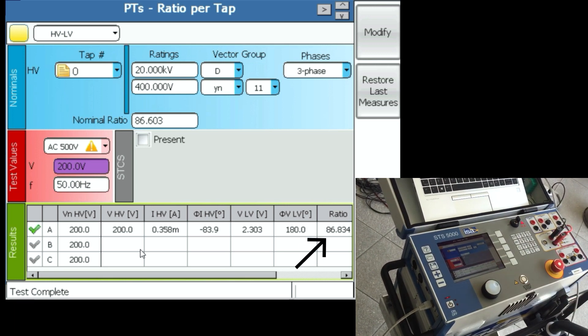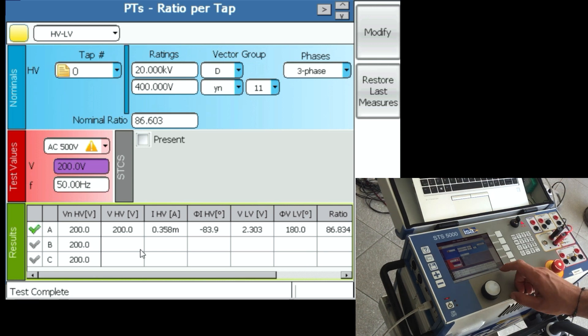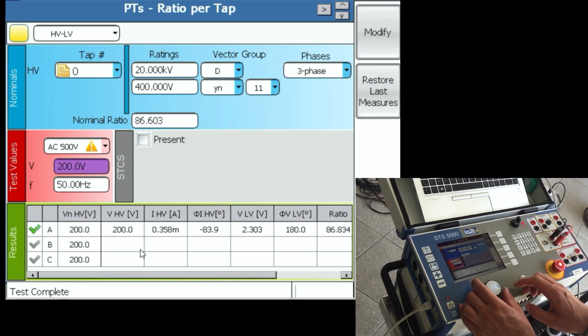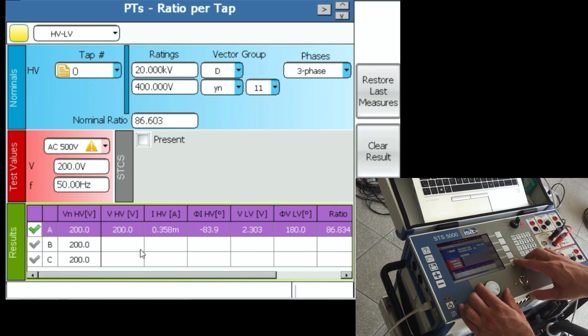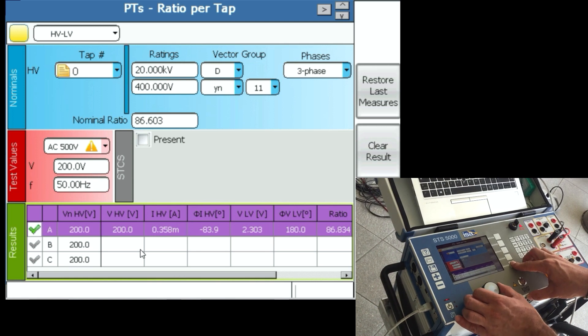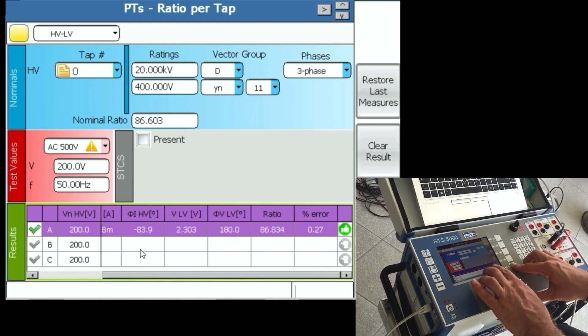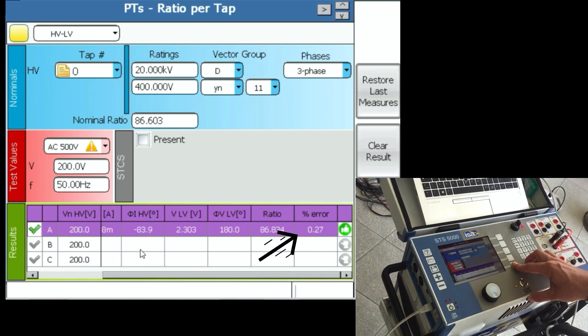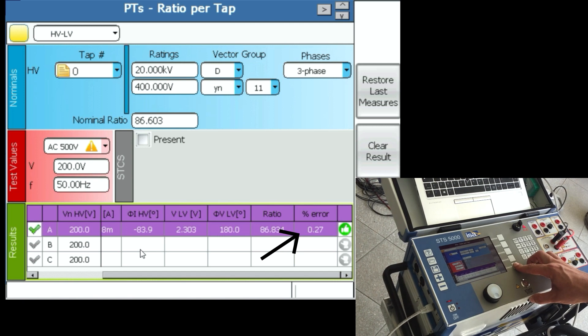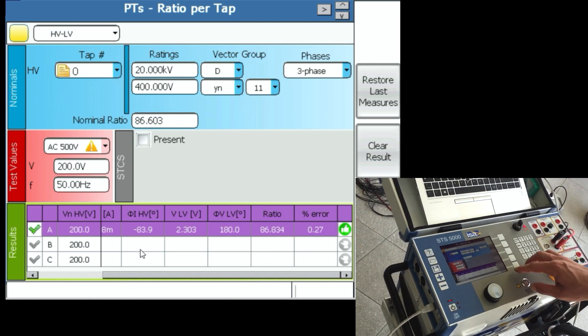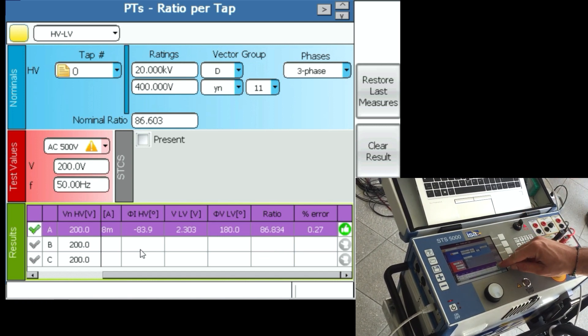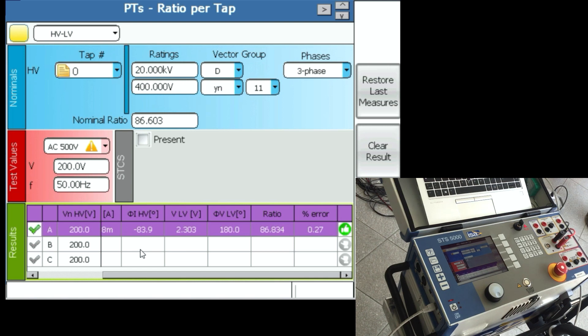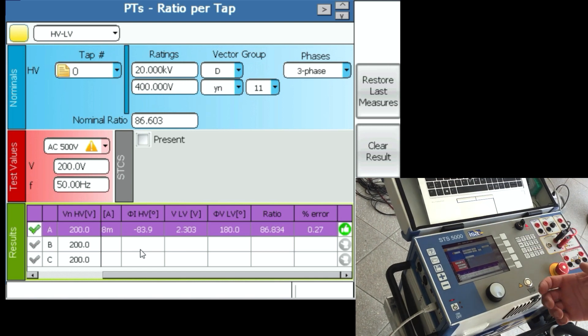We see 86.834 is a result for this phase. What we're going to do is again press scroll columns and rotate the knob, and we will see that we have an error of 0.27 for this phase, which is less than 0.5. That's why we have a thumbs up and a green thumbs up right here.